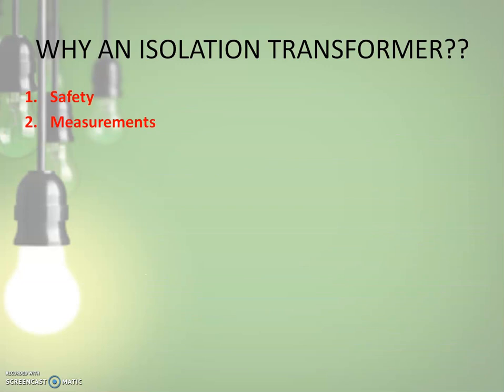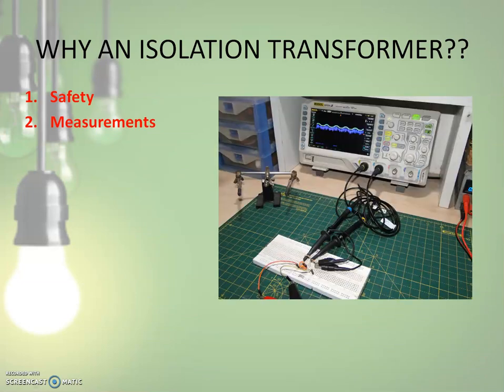And secondly, in measurements, it is very important to use isolating transformers when an oscilloscope measures signals in an electrical circuit or electronic circuit which is not galvanically isolated from the network, because the current circuit can be closed or short circuited between the oscilloscope common point and grounding.